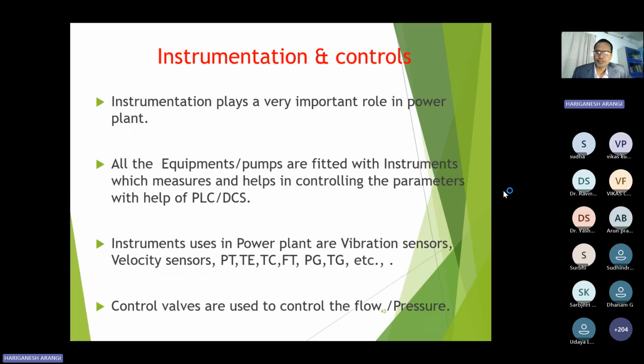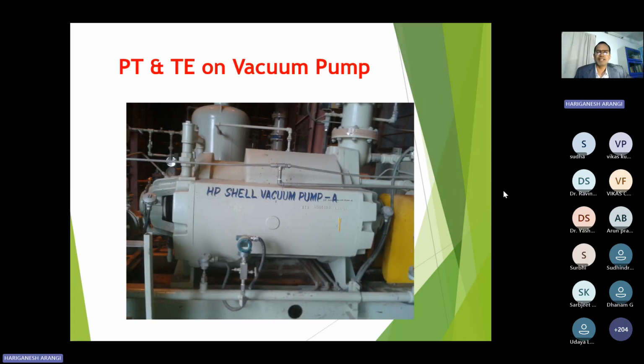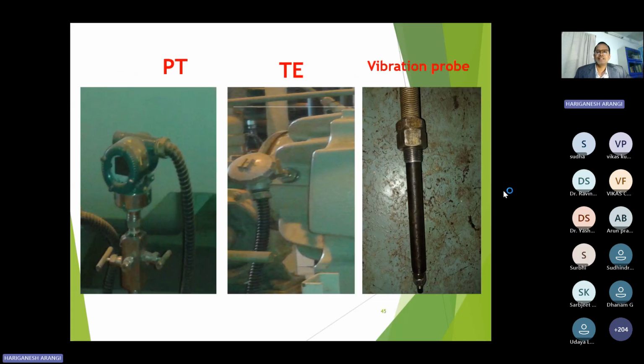With respect to instrumentation, we use pressure monitoring systems, temperature monitoring systems and flow measurement. That will be analog or digital. These are a few of the instruments to check. The first one is the pressure transmitter. This pressure transmitter is not only for monitoring; it will control several valves and the tripping system also. So this is one kind of control system.